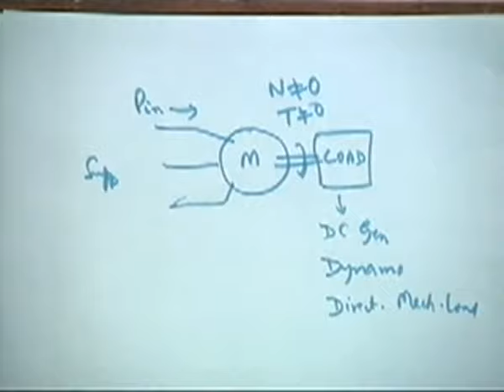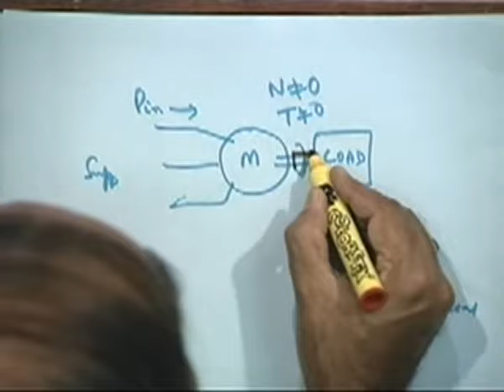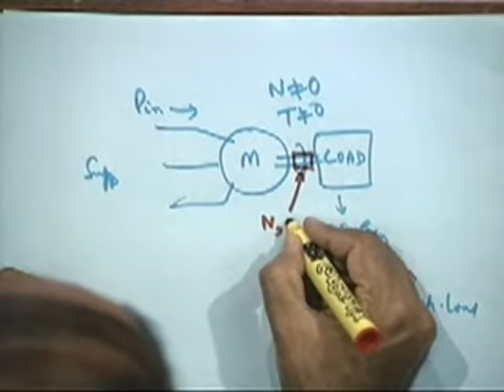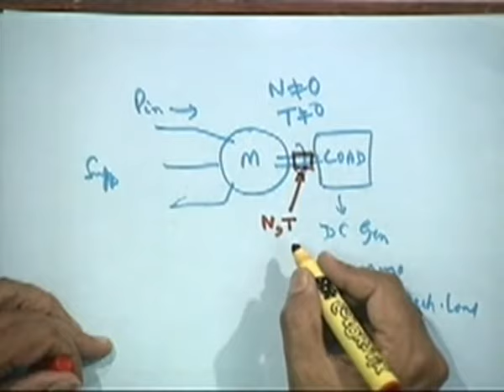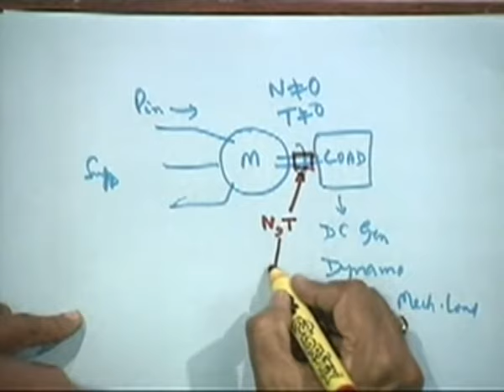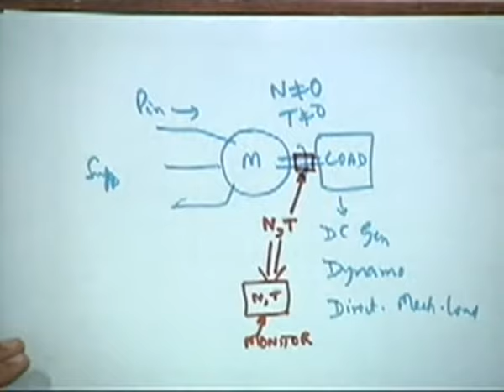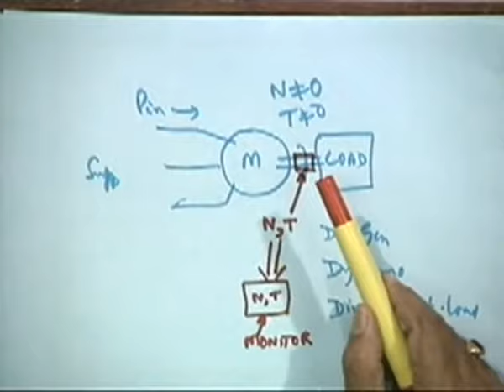But at the shaft, what measurements can you do? Speed you can measure. And if you have a sophisticated transducer, you can also measure torque. This torque is measured through a torque transducer, which is an electronic device. All these signals can be taken to a monitor which monitors speed and torque. Speed and torque are monitored in terms of voltages, but calibrated in terms of speed in RPM and torque in Newton meters. They are commercially available, so after loading you can do this.